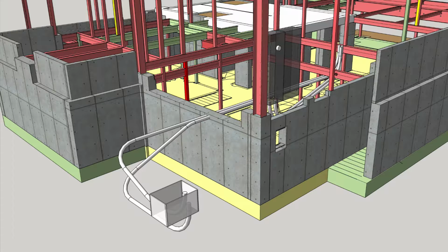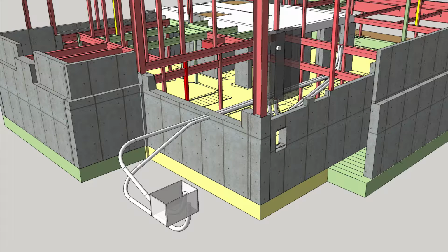In this third option, we were able to keep each conduit run to 270 degrees of sweep or less by establishing another pull point within the garage. However, the utility did not approve this as they want the conduit to run directly from their handhole to the service panel with no pull point in between. Back to the drawing board.